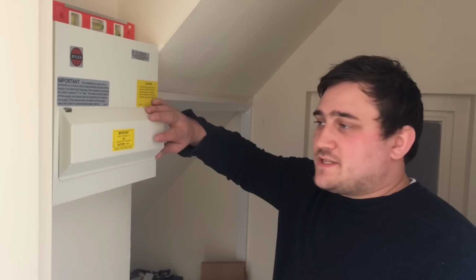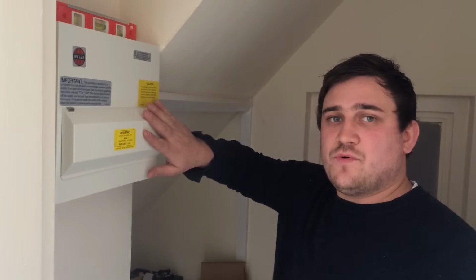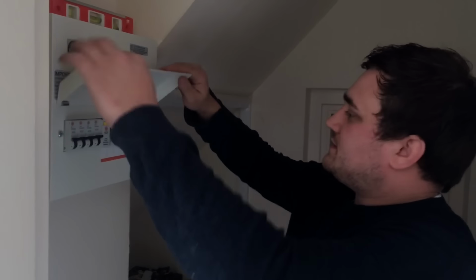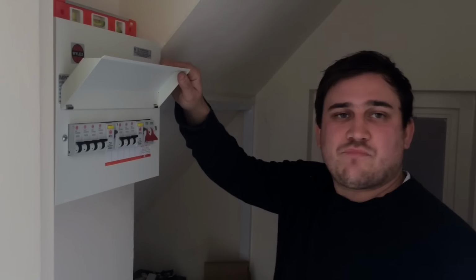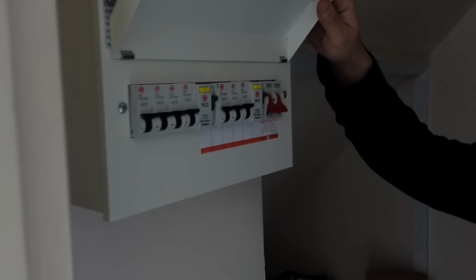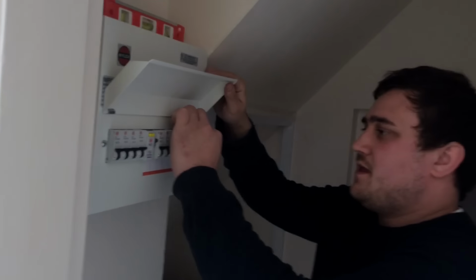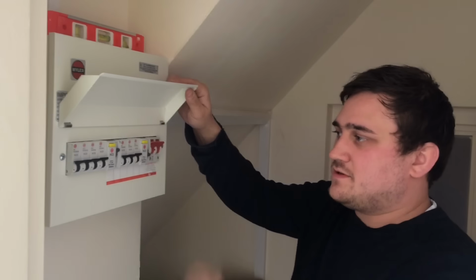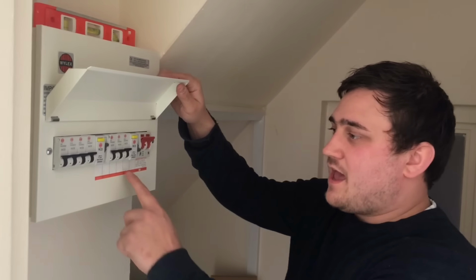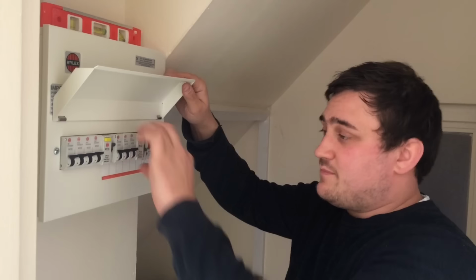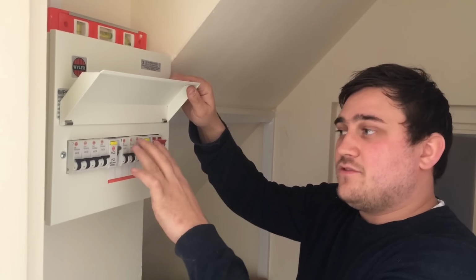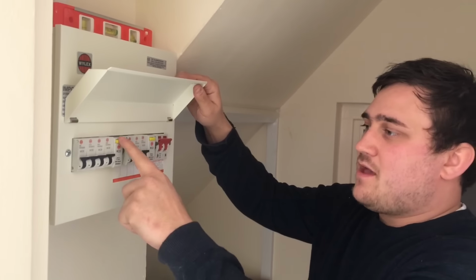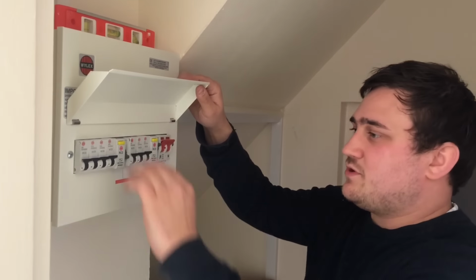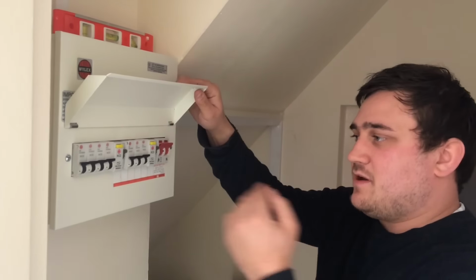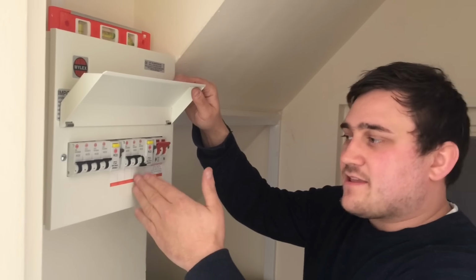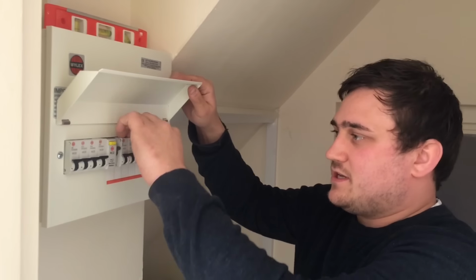Now that I've completed all my tests other than my functional tests, I've got a label at the board and I'll do this alongside my functional tests. So what I'll do is I'll break the main switch and go around and check that all the circuits have been isolated, and then I will use my test button on my RCD. I'll check the circuits that haven't been labelled yet. I'll check then, just them ones have gone off. I'll re-energise that. I'll then test this RCD, do the same principle with them circuits, and then as I'm labelling them, I'll individually go around and check that they all isolate the correct circuit.